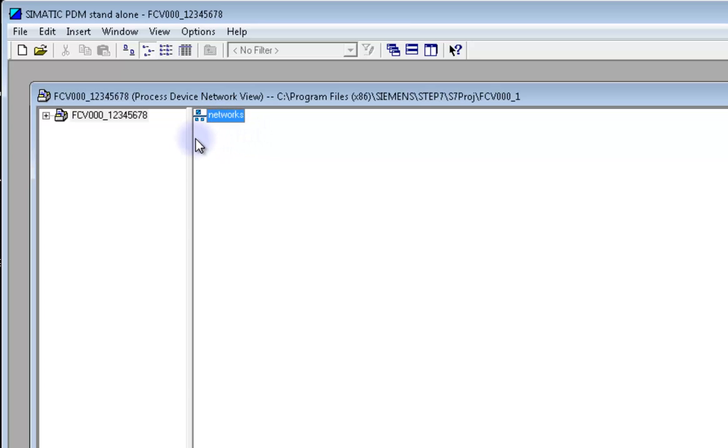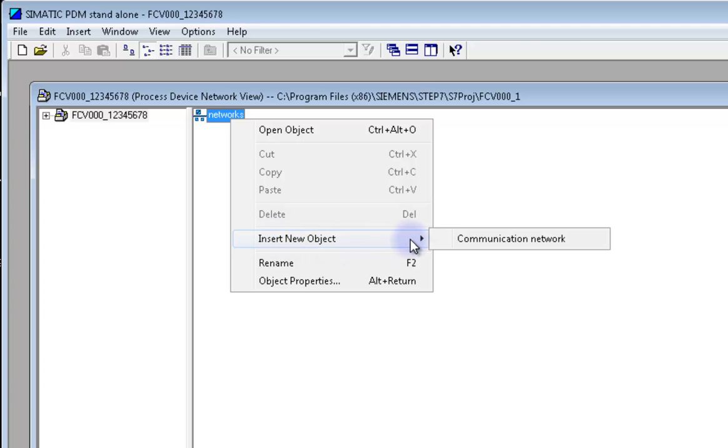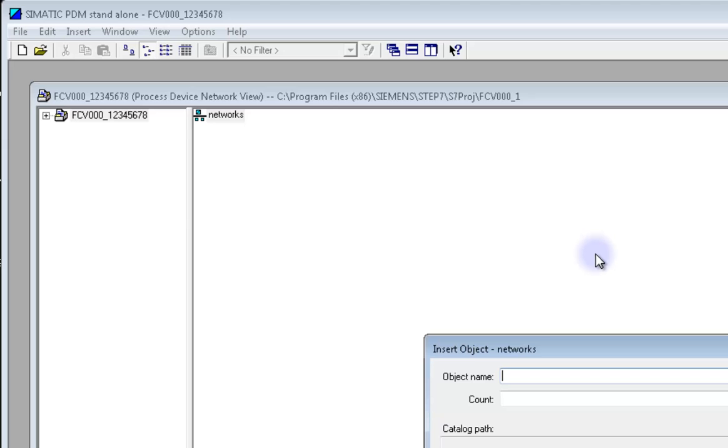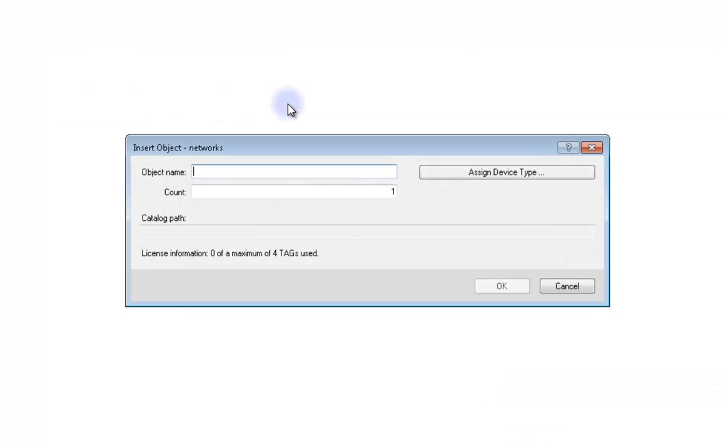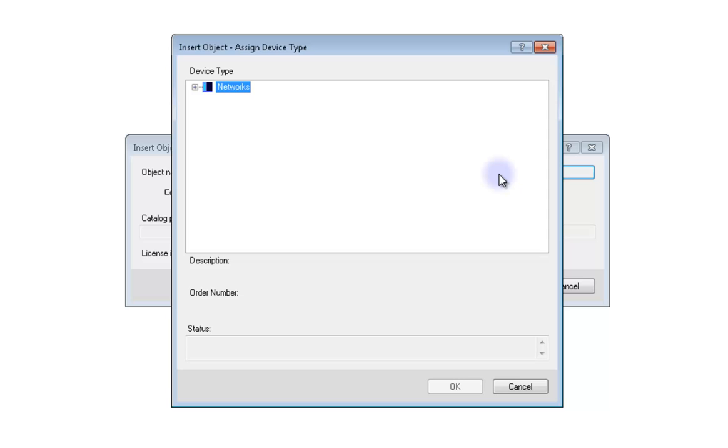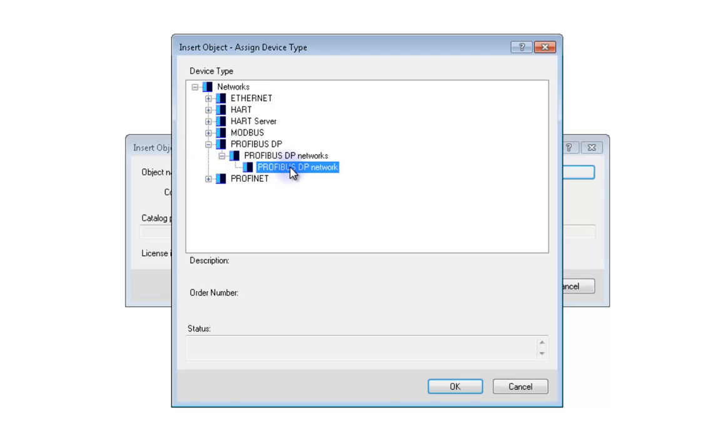Now right click on the New Network and click Insert New Object and Communication Network. This Insert Objects window will show up. First click Assign Device Type. Expand Networks and then Expand Profibus DP. Highlight Profibus DP Network and then click OK.